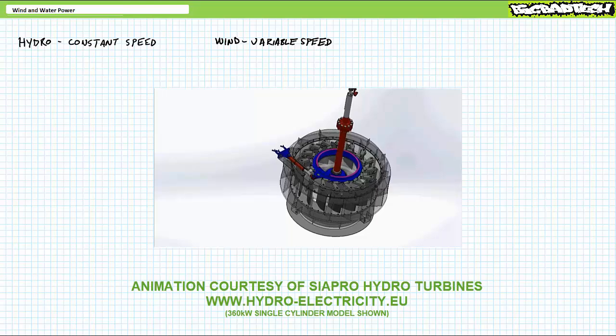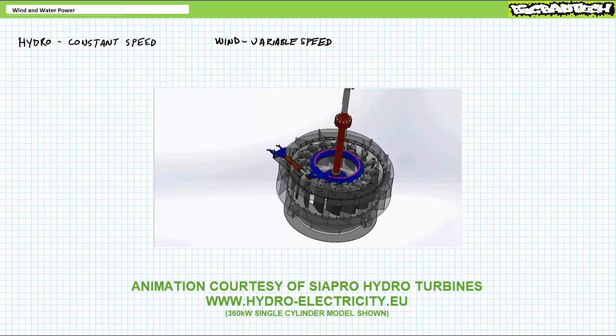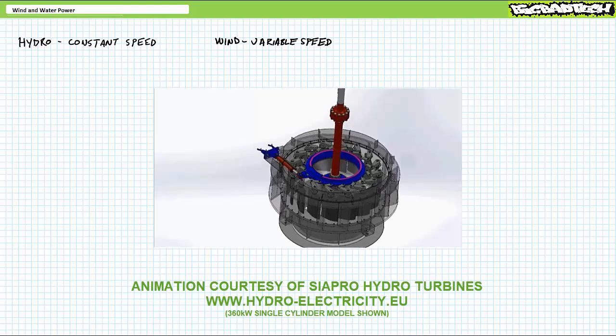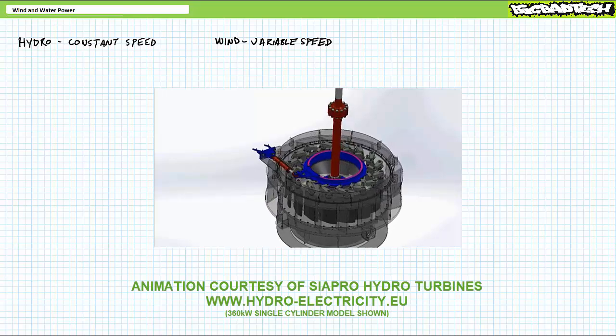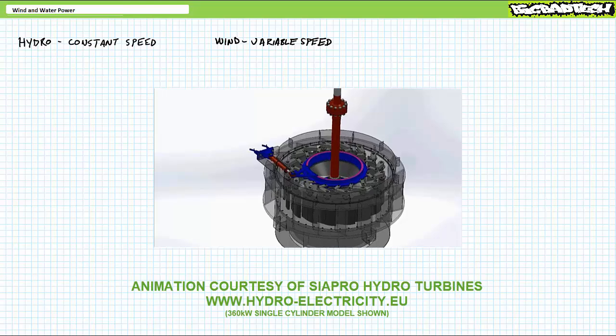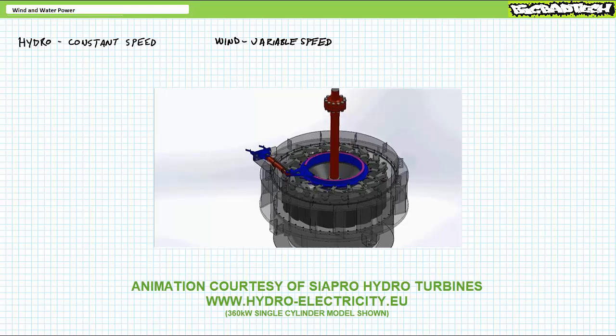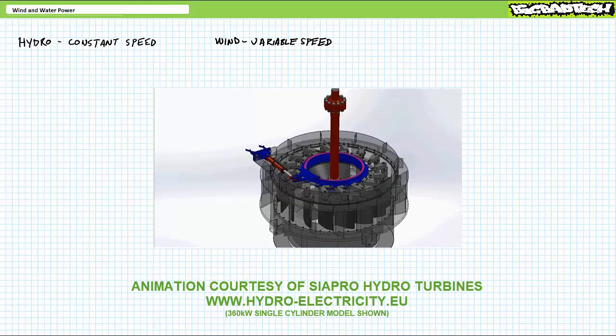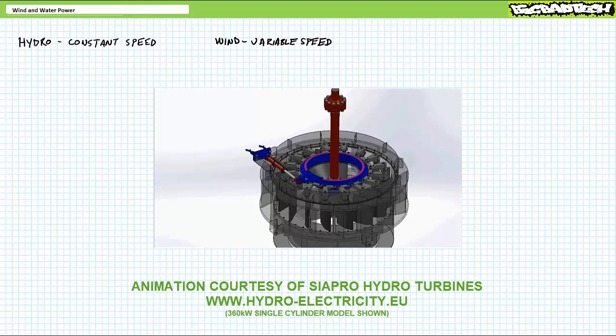This means hydropower turbines essentially operate by maintaining constant input from an available resource. The management of flow rate is largely performed by opening and closing what are known as wicket gates using a bull ring and two hydraulic cylinders. If one cylinder extends and the other retracts, they turn the bull ring such that the wicket gates open like Venetian blinds and allow more water in. Conversely, as one cylinder retracts and the other extends, the bull ring rotates in the opposite direction such that the wicket gates close and allow less water in.